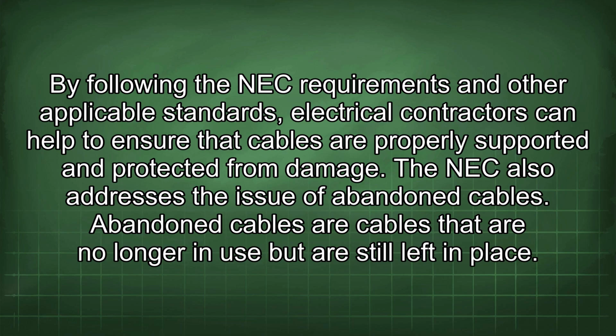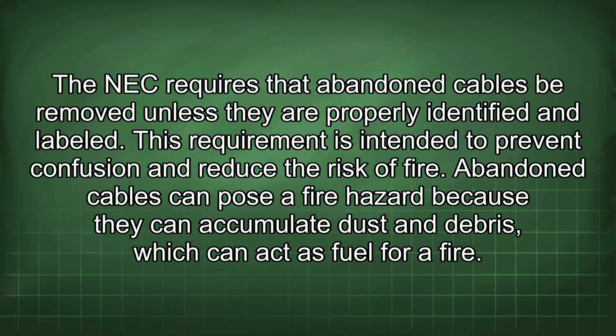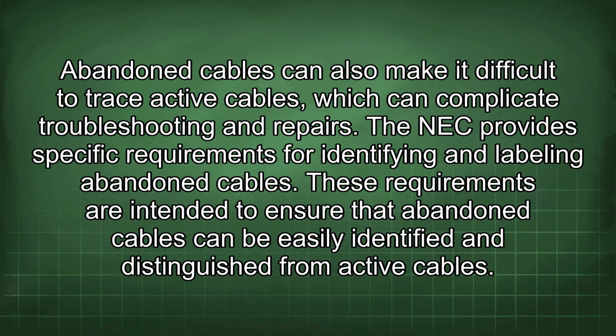Abandoned cables are cables that are no longer in use but are still left in place. The NEC requires that abandoned cables be removed unless they are properly identified and labeled. This requirement is intended to prevent confusion and reduce the risk of fire. Abandoned cables can pose a fire hazard because they can accumulate dust and debris, which can act as fuel for a fire. They can also make it difficult to trace active cables, which can complicate troubleshooting and repairs.